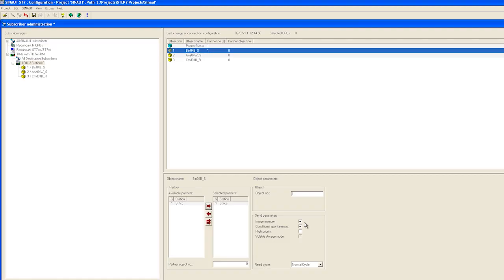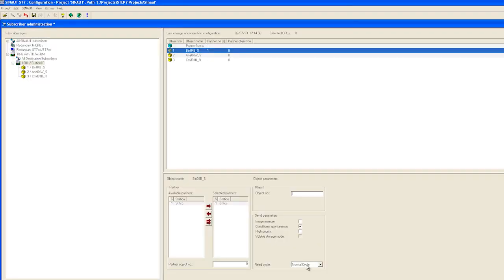If we uncheck this option we are choosing what is called the send buffer principle. The send buffer principle means that all values including the timestamp are buffered on the TIM and transmitted at the given time. Finally, we recommend the fast read cycle for messages and alarms. This guarantees the data from the CPU will be gathered immediately.